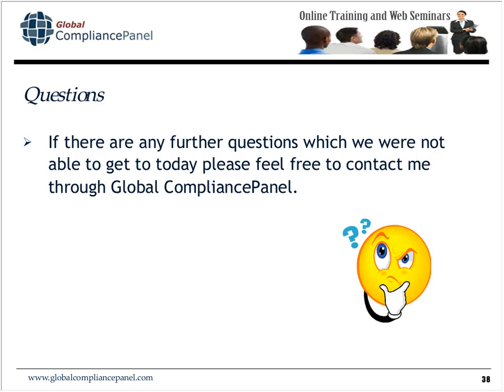Here it is. For implantable medical devices, is losing the serial number information considered a major violation which requires a recall? That's a great question. I'm only going to speak anecdotally and not based on experience. Fortunately, all the medical devices I've ever been involved in from a personal or consulting basis have been non-implantable. However, it is a regulatory requirement that implantable devices maintain the ability to be serial numbered. So I'm going to take the worst possible case scenario here and say that this implantable medical device not just did not have the serial number on it, but the patient into whom it's been implanted, there's no more link between him or her and the device that's inside of them. That is considered a major violation and would require recall.